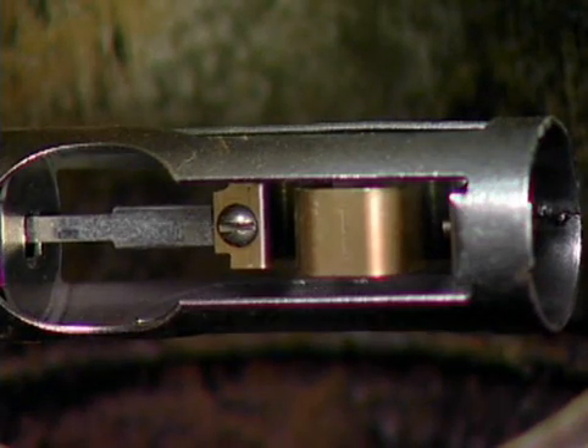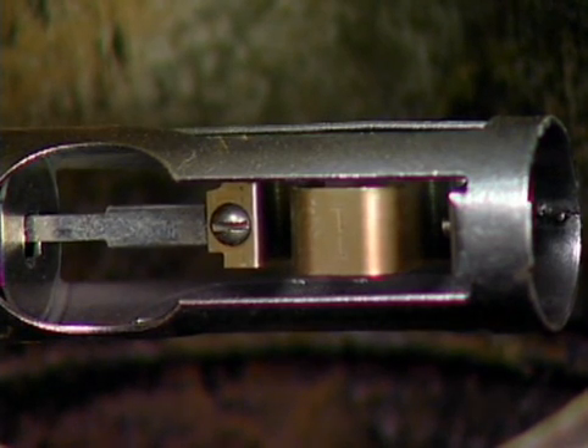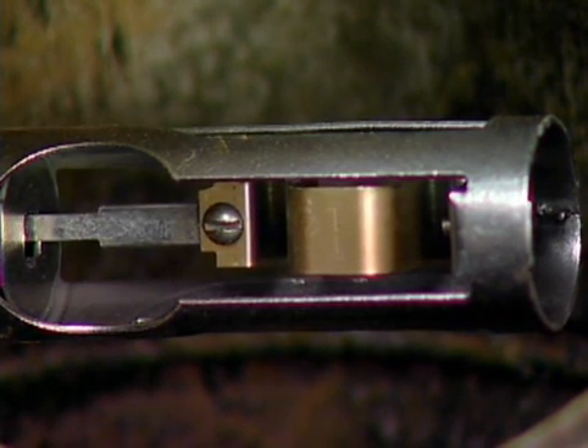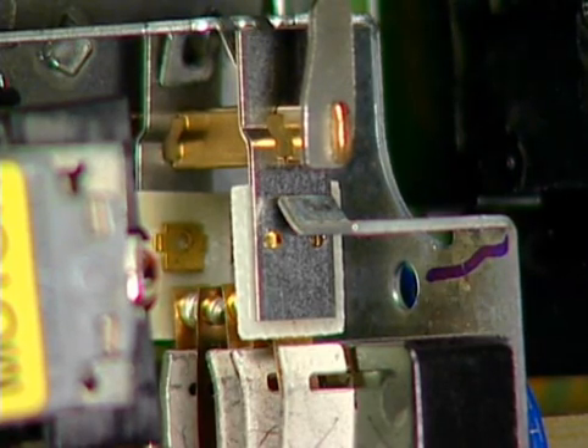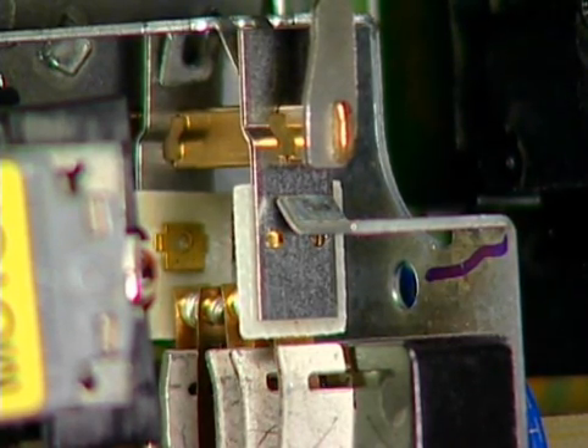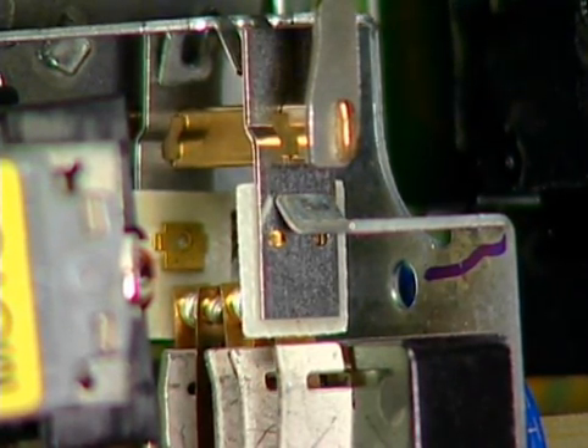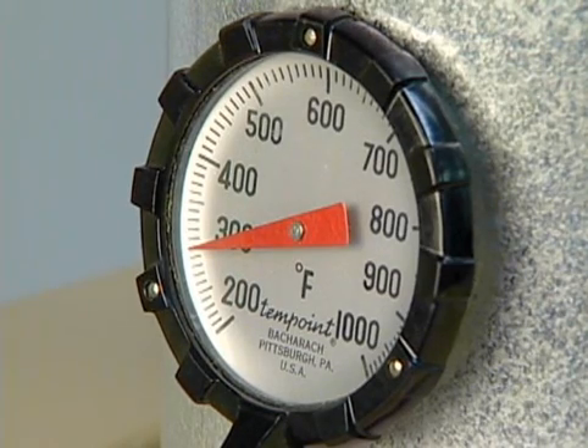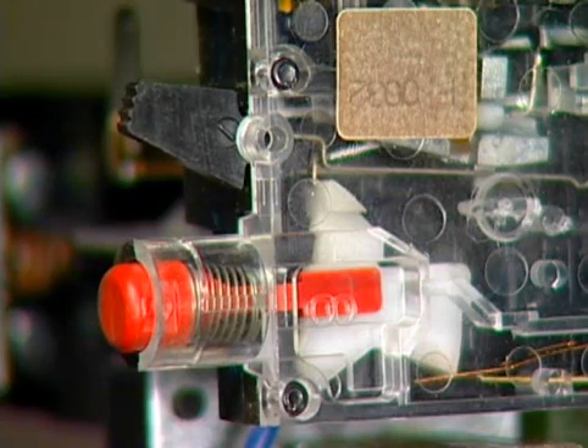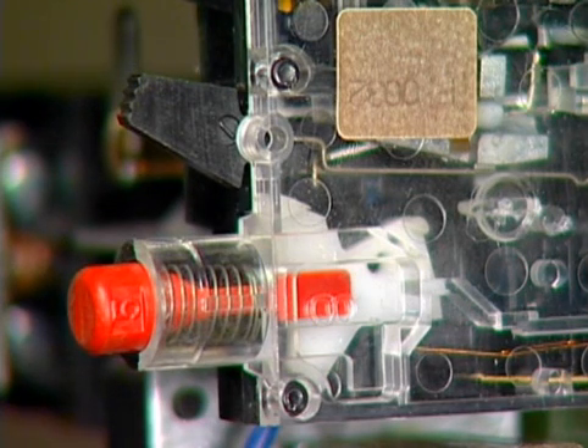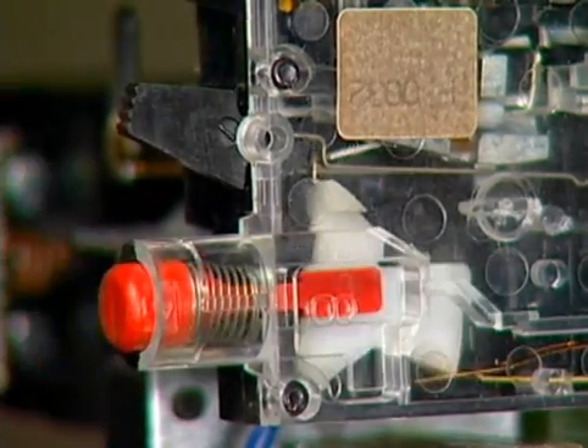When the burner operates, heat rises and passes over the bimetal element, which expands. This forces motion in a drive shaft which closes contacts that enable the burner to continue operating. If the bimetal is not sufficiently heated, a built-in safety switch shuts off the burner in approximately 75 seconds. It cannot be started again until the safety switch is manually reset.